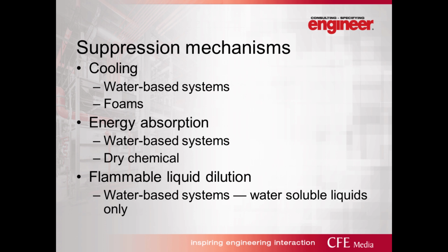So what are some of the mechanisms by which fire suppression systems operate? And remember, from a fire suppression system standpoint, we're not just talking about sprinklers. There are other suppression systems out there that are appropriate given the hazard that we're looking at. We'll talk about that a little bit more. But here are some of the suppression mechanisms that may occur depending on the type of system that you're using. Cooling. Obviously, cooling the fire is extremely important. If you know your basic combustion science at all, and I wish I would have put a diagram up here on the slide for you, the concept of the fire triangle has been around for forever. And basically, the triangle is three items that are required for combustion. The first is oxygen, the second is fuel, and the third is heat.